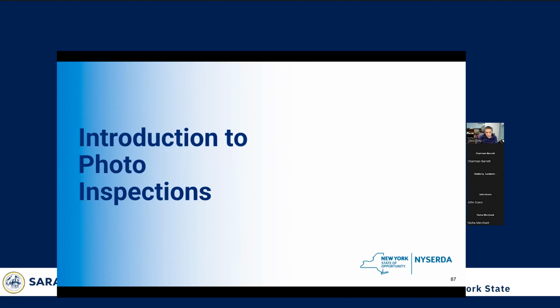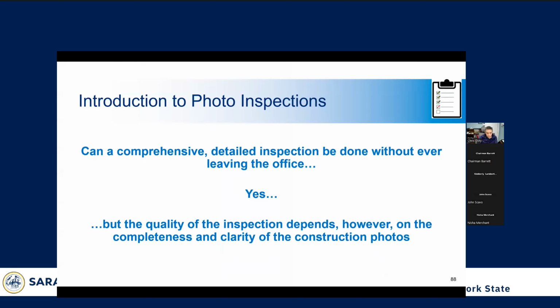So now we're going to go over just a few slides on photo inspections, and then we'll jump into common errors that we see. Can a comprehensive inspection be done by looking only at photographs? The answer to this is yes, but it very much depends on the quality and the quantity of the photo collection. Photo inspections are done through the quality assurance program for NYSERDA to save dollars by not making someone go to an in-person 4-hour inspection. Something to keep in mind is that sometimes well-built systems will fail a photo inspection because the quality or the quantity of photos was not good enough to make a determination. So it's on the contractor to take the proper photos, and the proper quantity of photos, for someone to make an evaluation.